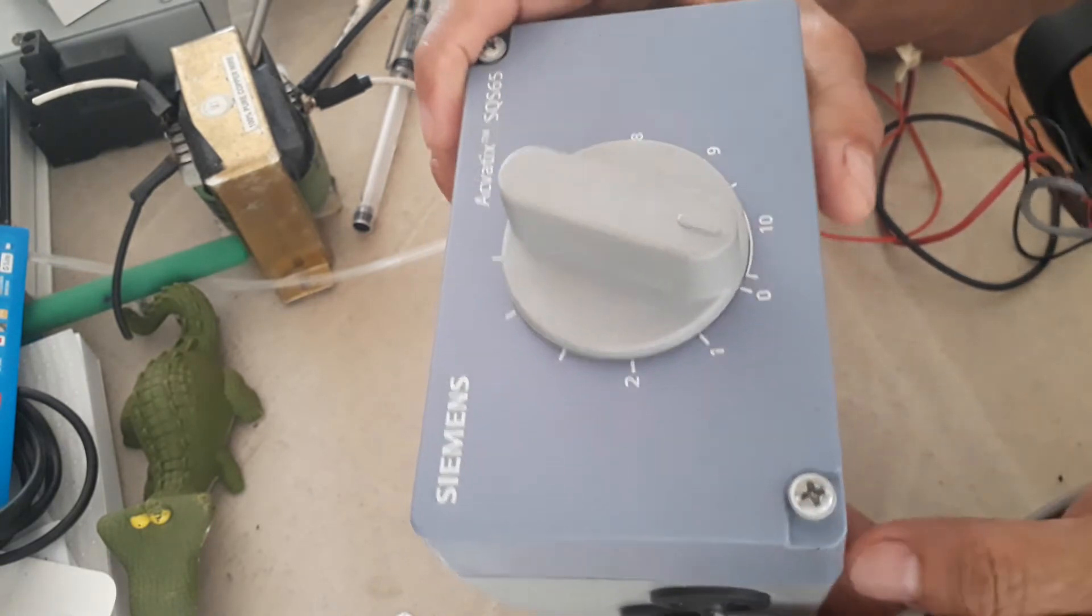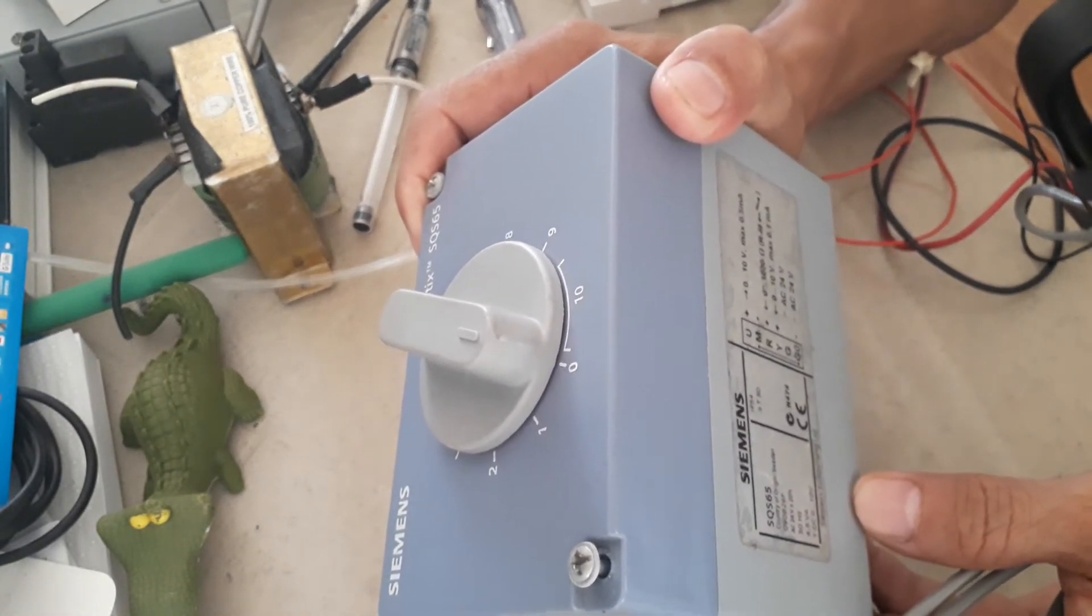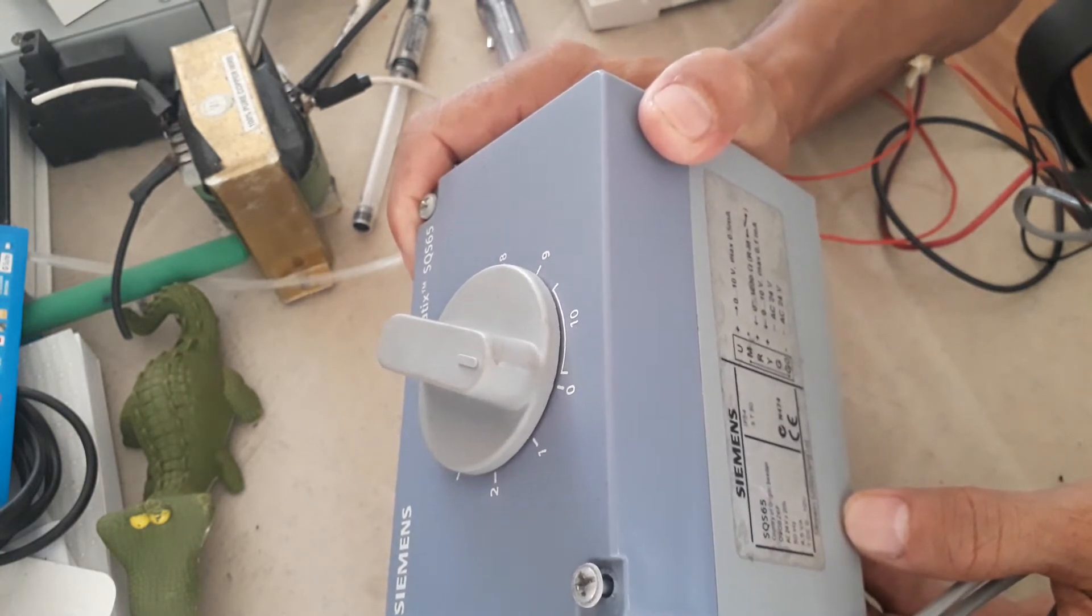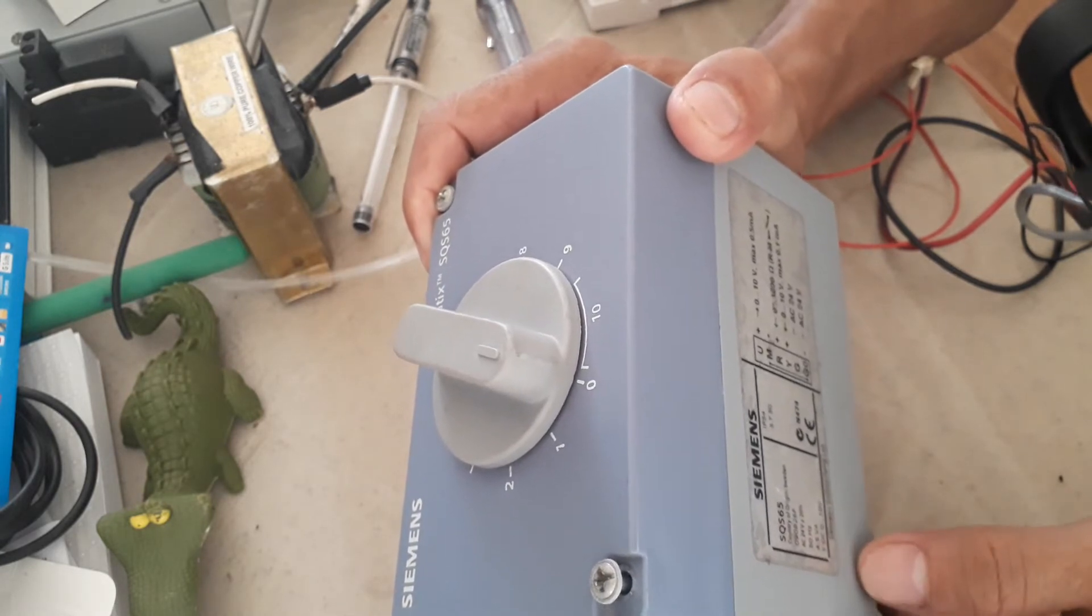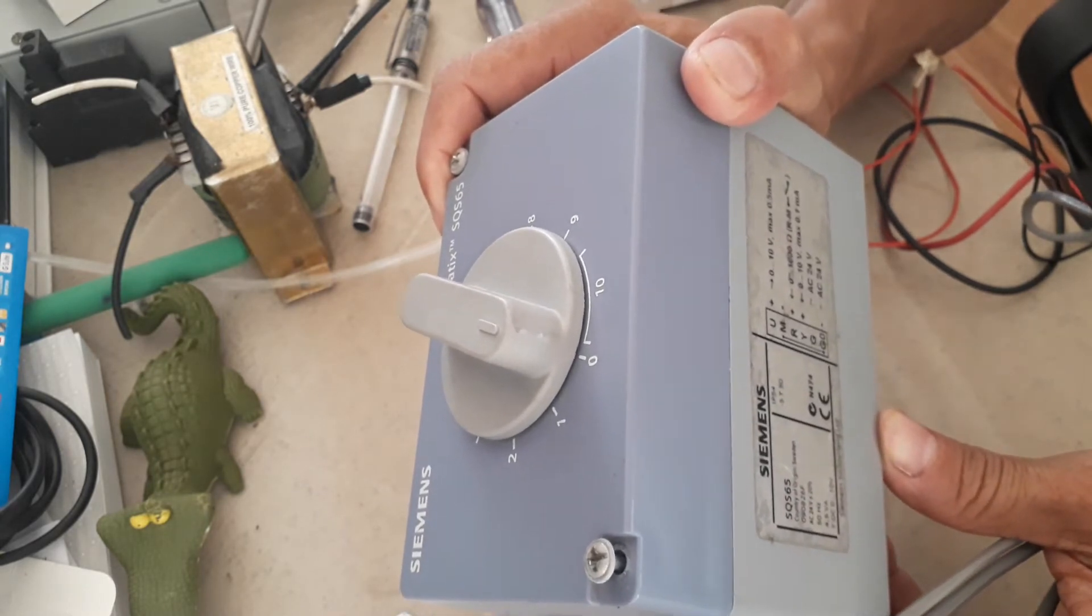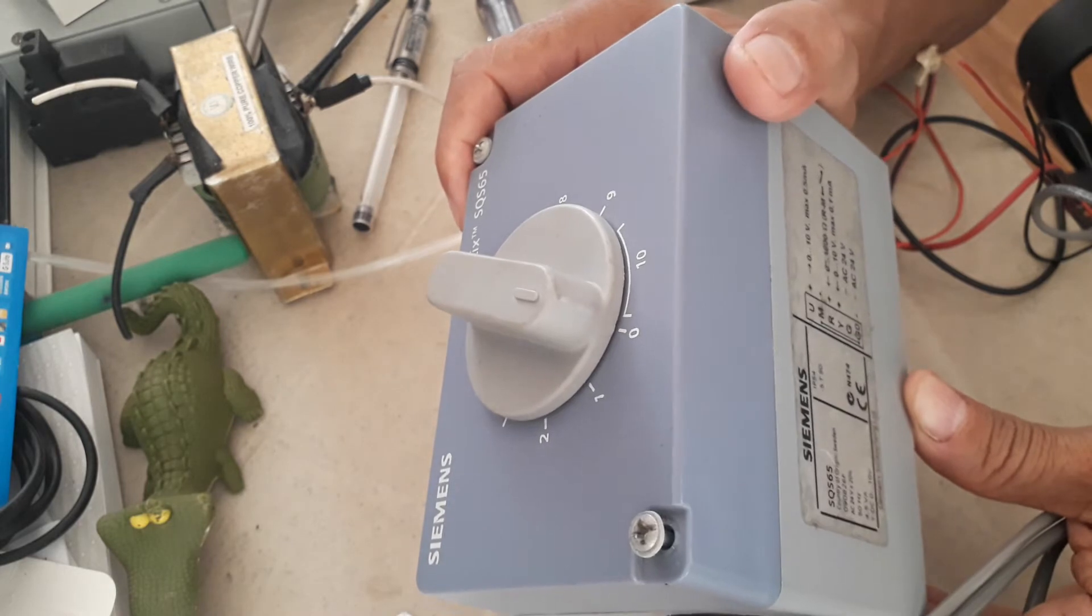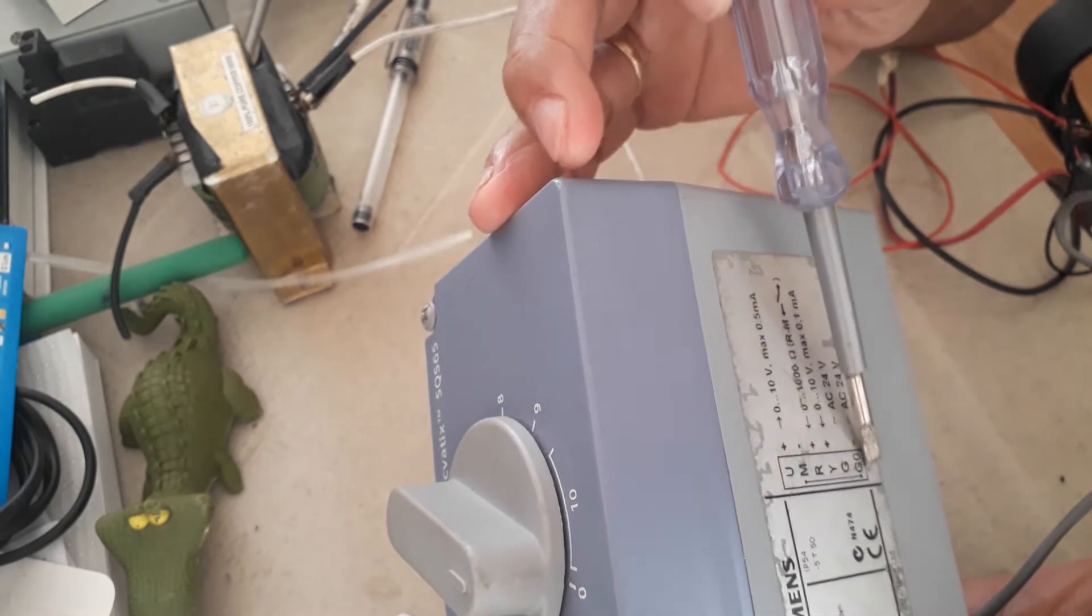What are the terminals for this valve actuator? As a BMS engineer, you will always pay attention to the details. Y is 0 to 10 volts. That meaning, that is the control signal that your DDC will give to this valve actuator. Power supply is 24 volts AC. This is IP54, meaning you cannot install this outside. You have to install it in a mechanical room. But outside installation, you cannot install this one because this is not IP65 or IP67. What are the terminals? I have here U, M, R, Y, G, G0.